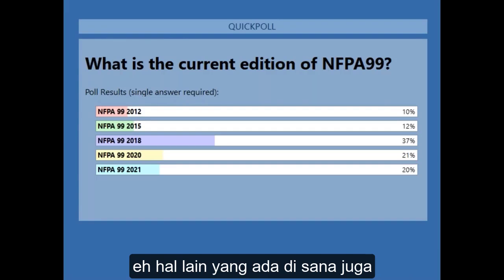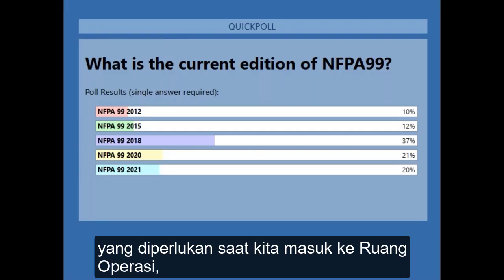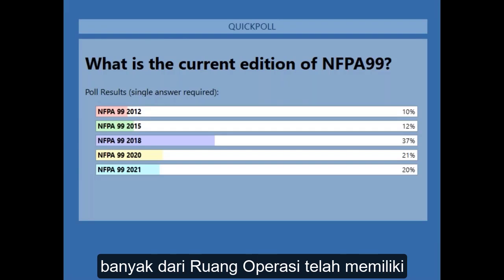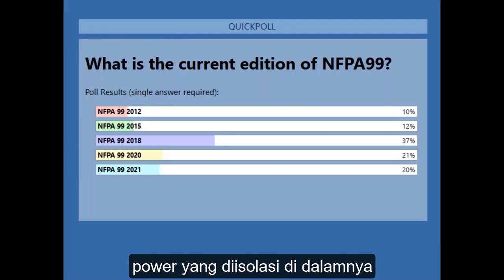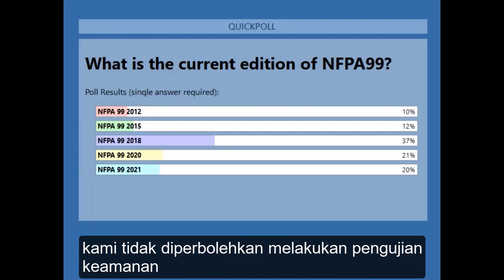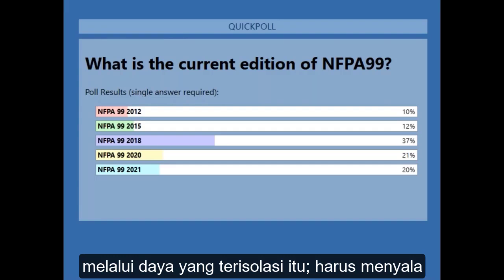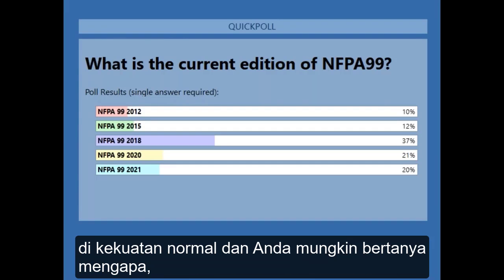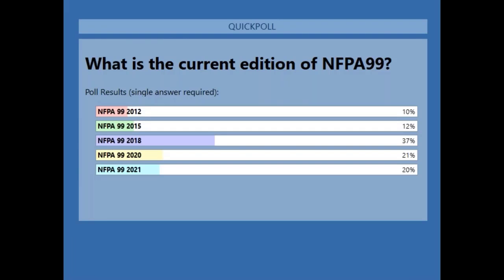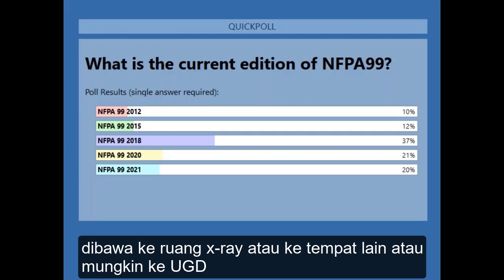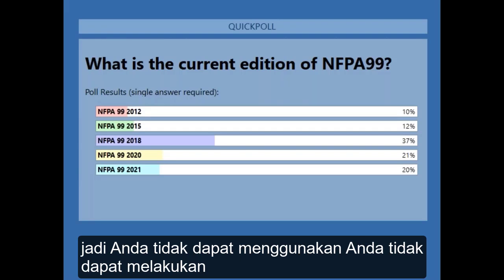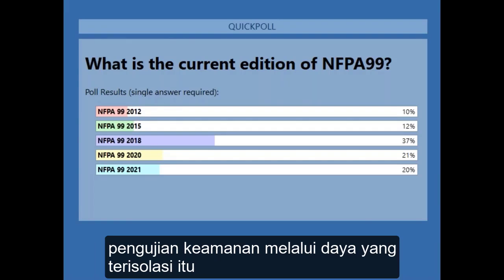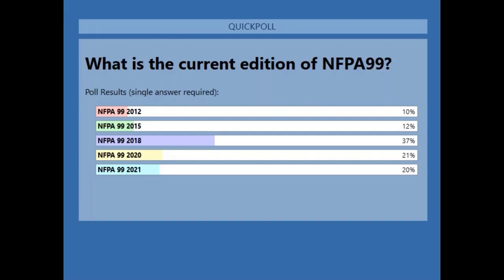Another thing that is required when we go into the OR: many of our ORs have isolated power in them. We are not allowed to do safety testing through isolated power. It has to be on normal power. And you may ask why. Well, there are times you may see an anesthesia machine roll into an x-ray room or somewhere else, or maybe down to your ER. So you cannot do your safety testing through that isolated power.